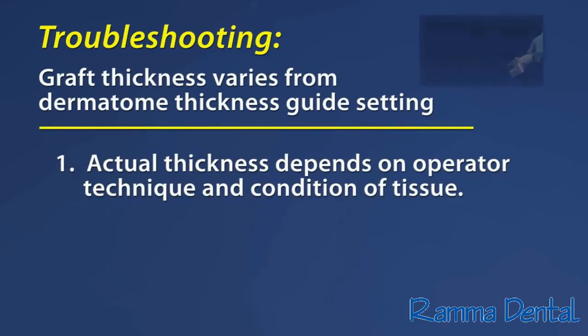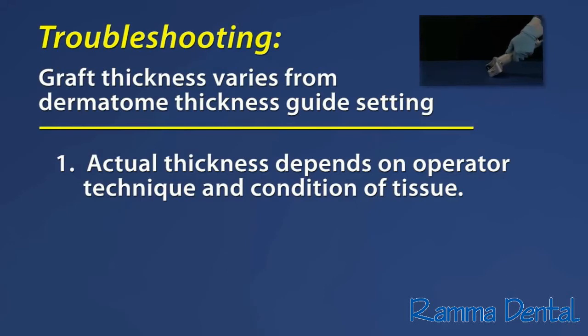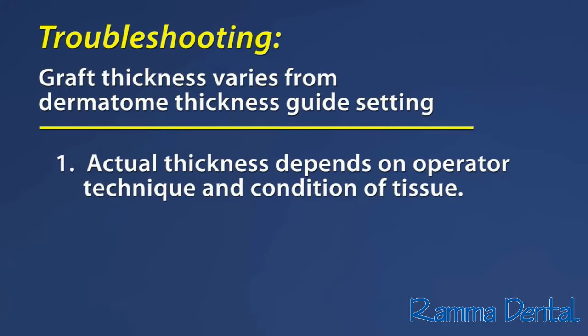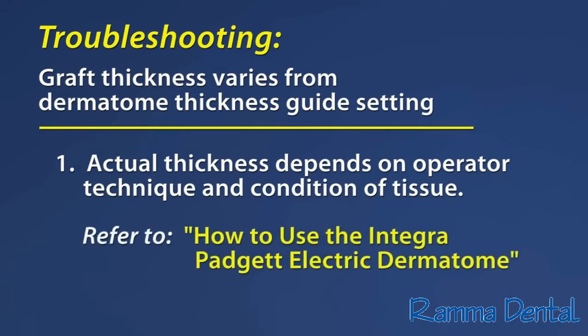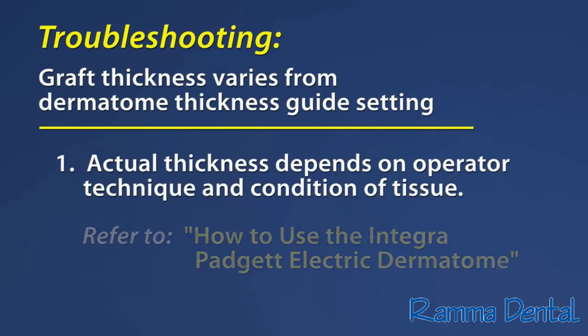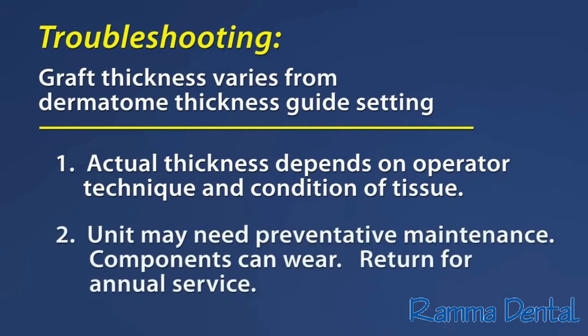The actual graft thickness varies from the Dermatome Thickness Guide setting. 1. The actual thickness of the graft is highly dependent upon operator technique and the condition of the tissue being harvested. Refer to the section How to Use the Integra Padgett Electric Dermatome for additional details. 2. The dermatome mechanism that controls the graft thickness is factory set to provide proper performance and includes components that may wear after repeated usage. To correct such issues, the dermatome must be returned to an Integra Padgett Dermatome Repair Center for service. Annual preventative maintenance is strongly recommended.